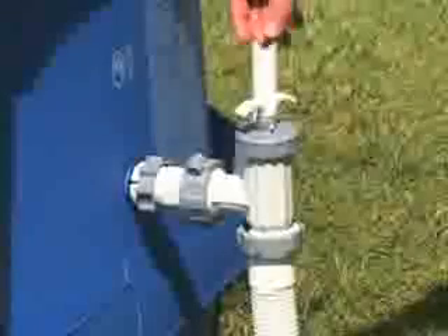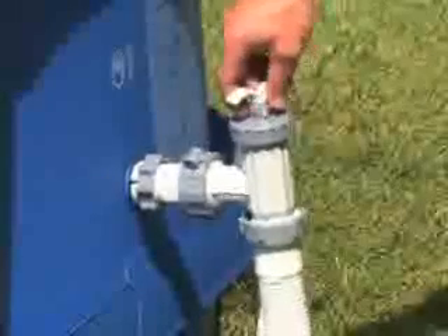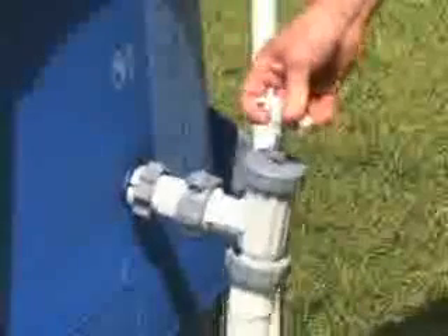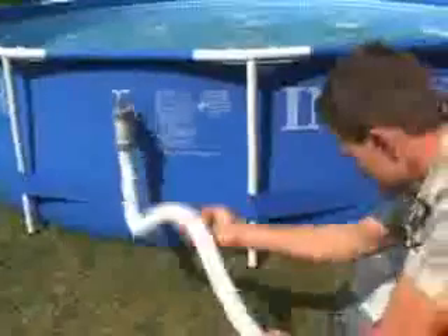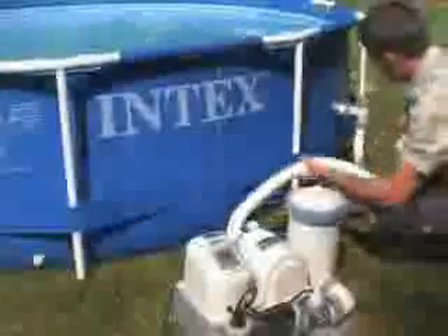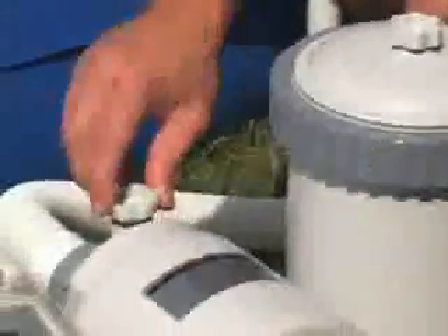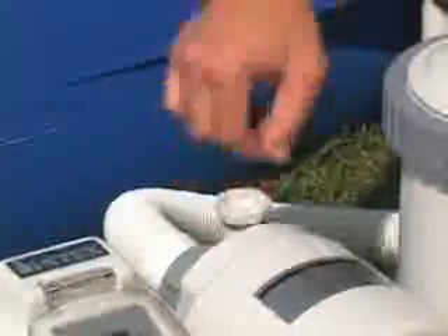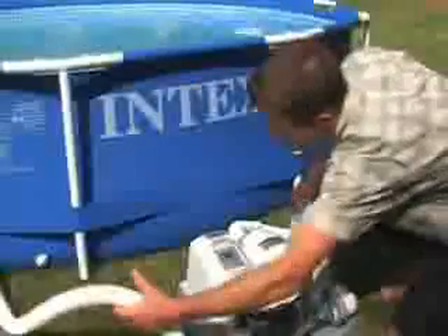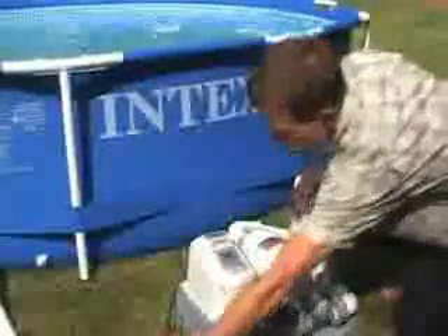First, make sure all connections are secured and remove the black hat-shaped hole plugs. Now, reopen the plunger valves. To prevent airlock, open the lower plunger valve first and then the upper valve. Make sure to follow the instructions in the manual to release air trapped in the hoses and unit. The air release valve is on top of the filter tower, and an additional air release valve is located just above the hose connection on the motor. It may be helpful to gently shake the hoses in order to release all the trapped air.